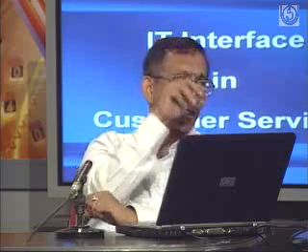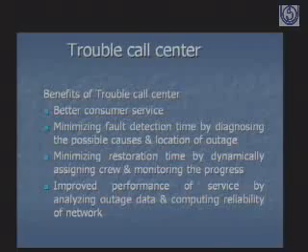If I get a complaint from a particular customer or group of customers, if I get a complaint from 3 or 4 customers, and if all these 3 or 4 customers are connected to a DT, we can reverse trace and consider that DT is at fault. If I get 4 calls from 4 different DTs, but on the same 11 kV feeder, we can consider that this 11 kV feeder may be at fault. This is called reverse tracing of the fault.